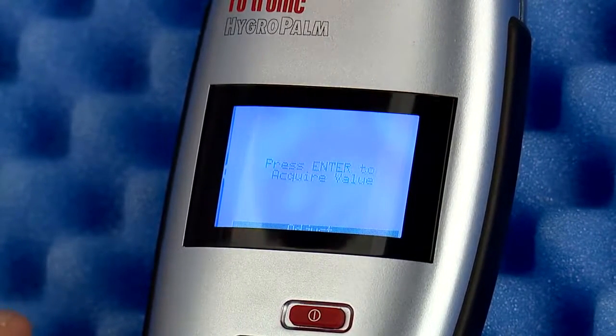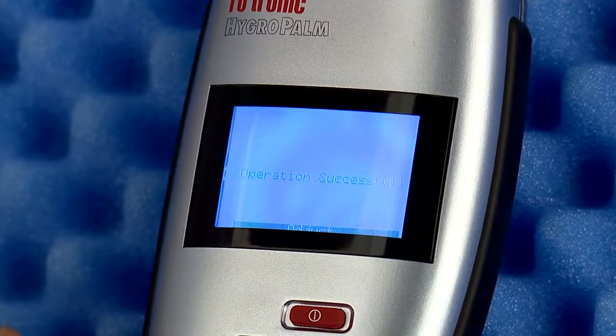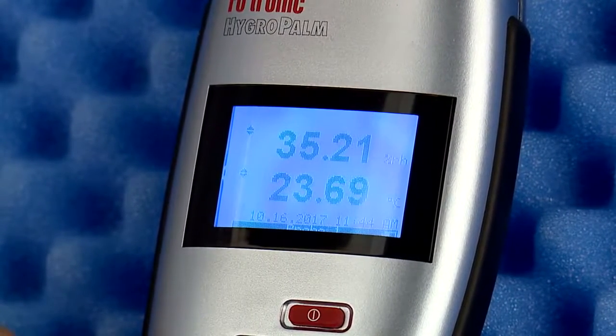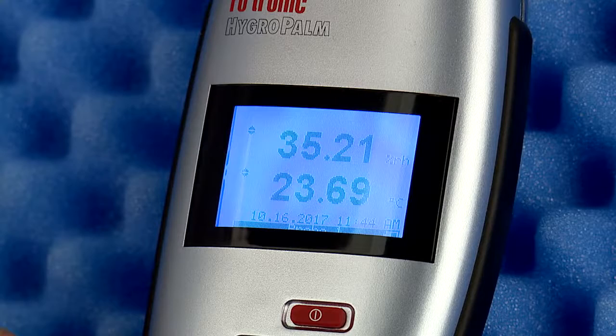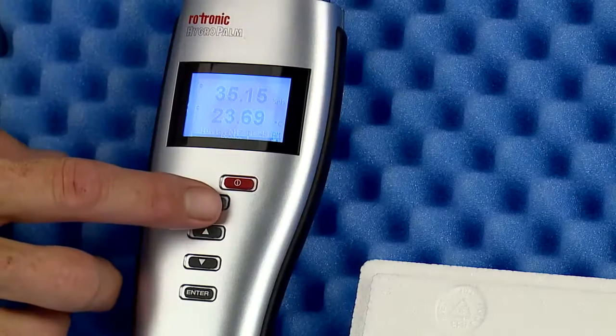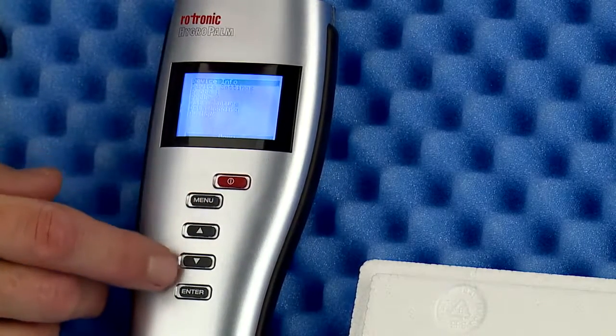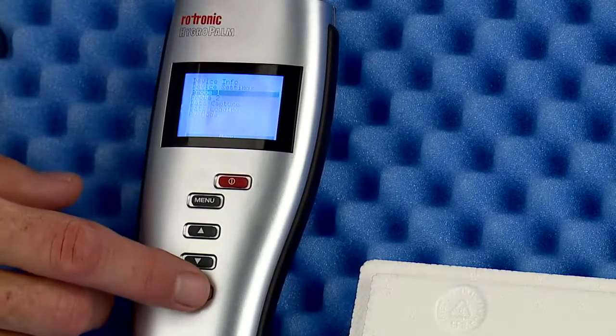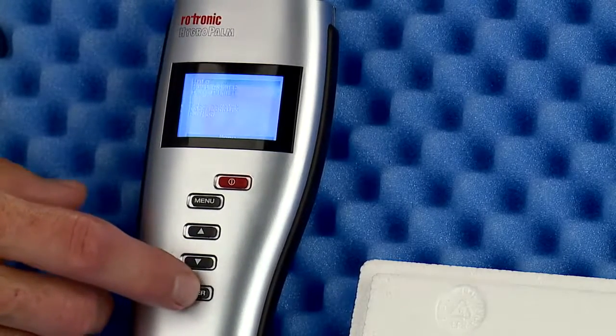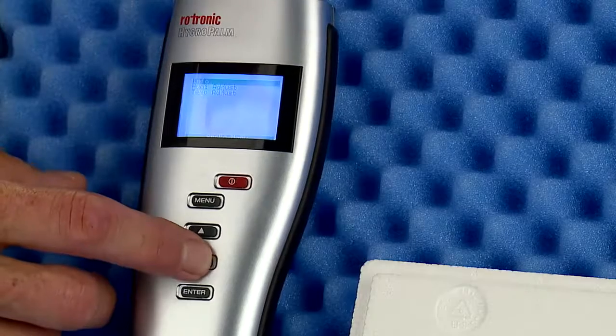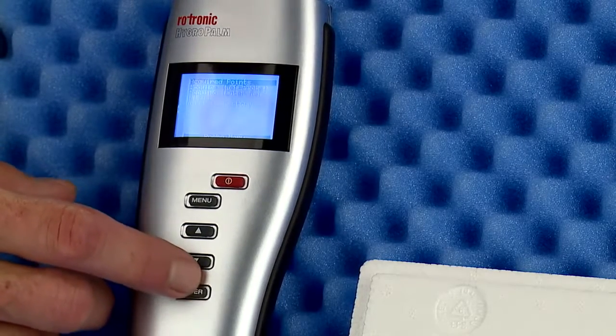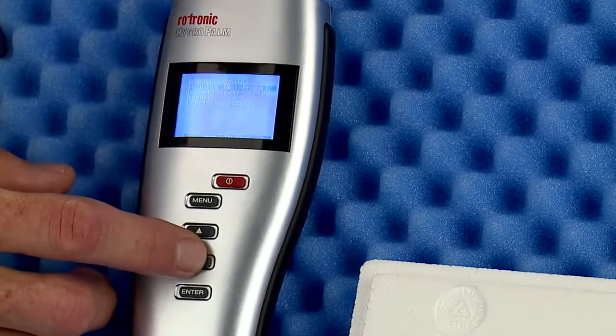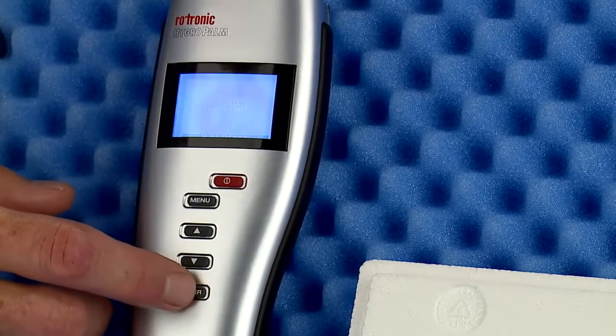Repeat the above steps with each humidity value you wish to use for calibration. Once all points are acquired, and remember to give each point approximately 45 minutes to stabilize, you can move on to the adjust step if necessary. Apply the adjustment if any saved point varies from the reference by more than plus or minus 0.8% relative humidity. As you can see, the calibration of the HP23 AW instrument is simple and straightforward.